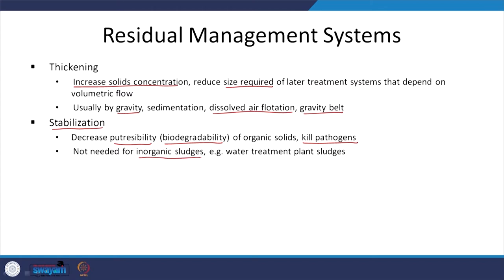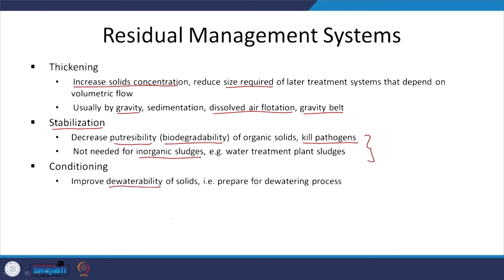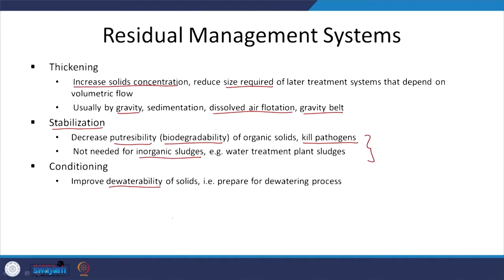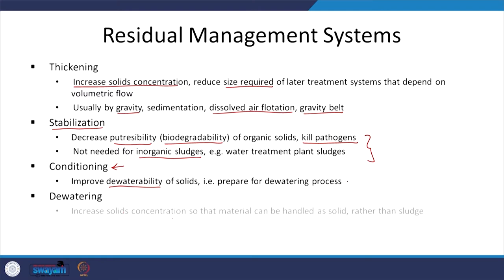If it is inorganic sludge from primary treatment during water treatment, or if it is grit and such, we are not going to look at that — specifically for organic sludges. So conditioning: improve dewaterability of solids. Later I want to dewater this solid. Why? I want to decrease the volume I am going to handle, and rather than sludge I want to handle solids which are easier to handle. So to do that I am going to condition it — improve dewaterability of the solids — typically by adding the relevant cations or different polymers.